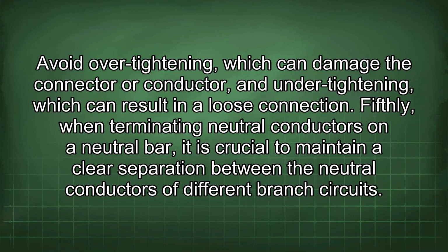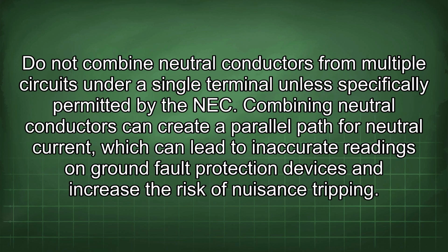Fifthly, when terminating neutral conductors on a neutral bar, it is crucial to maintain a clear separation between the neutral conductors of different branch circuits. Do not combine neutral conductors from multiple circuits under a single terminal unless specifically permitted by the NEC. Combining neutral conductors can create a parallel path for neutral current, which can lead to inaccurate readings on ground fault protection devices and increase the risk of nuisance tripping.